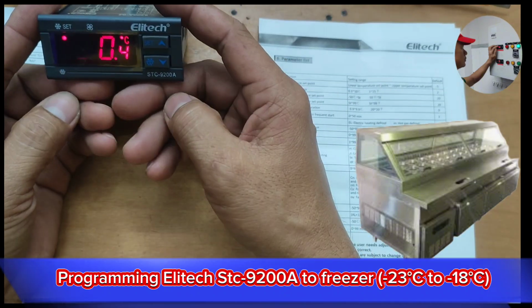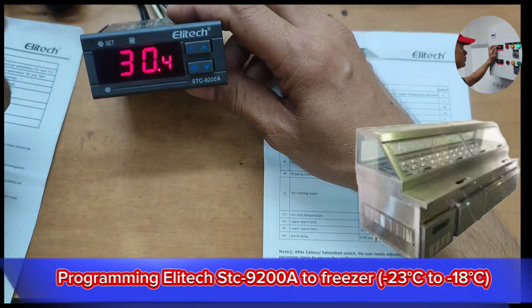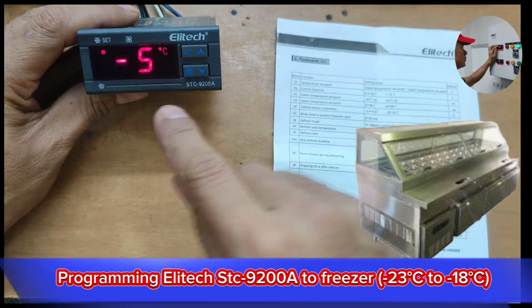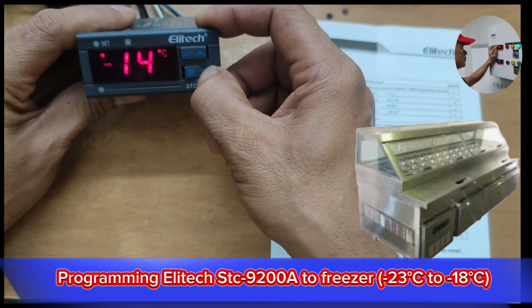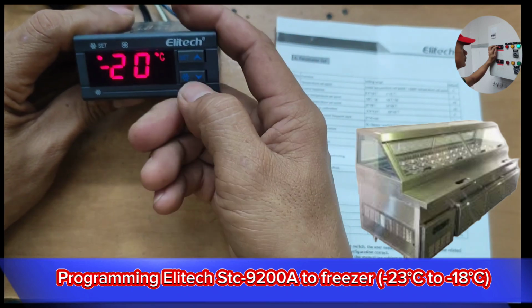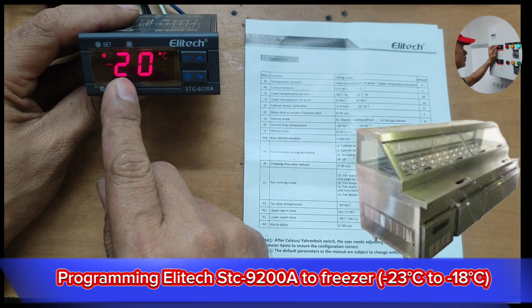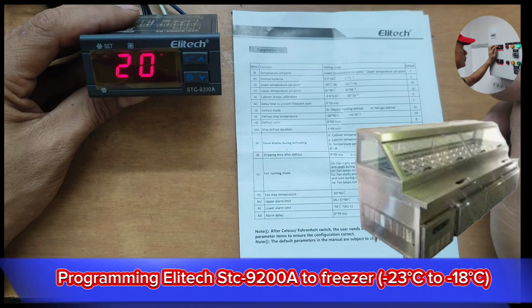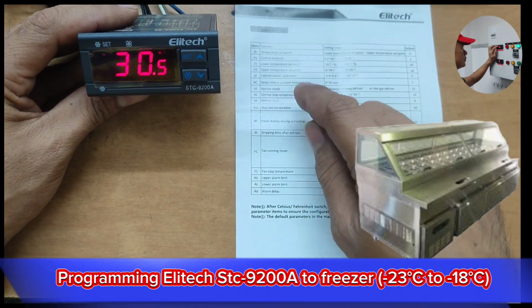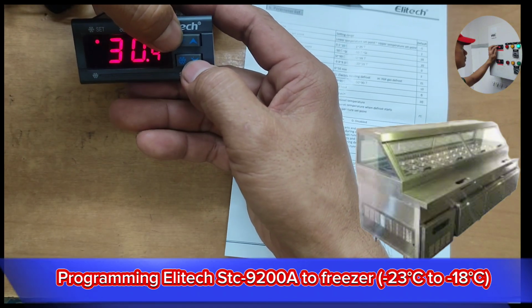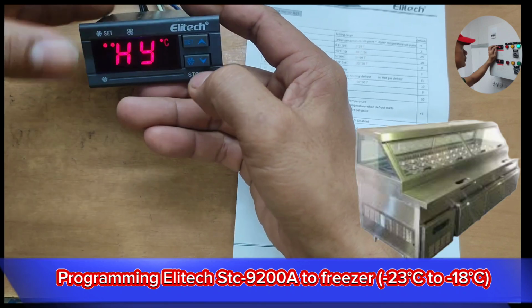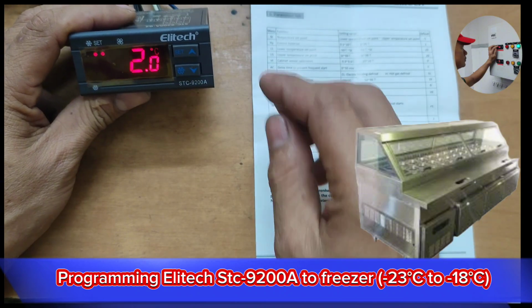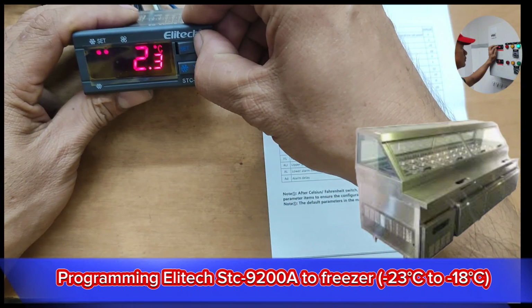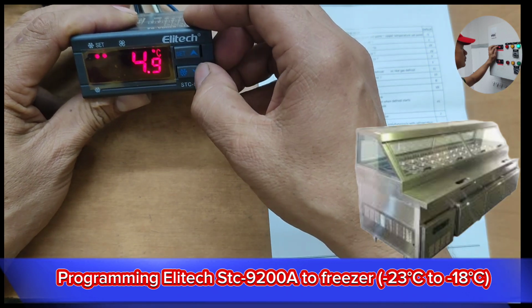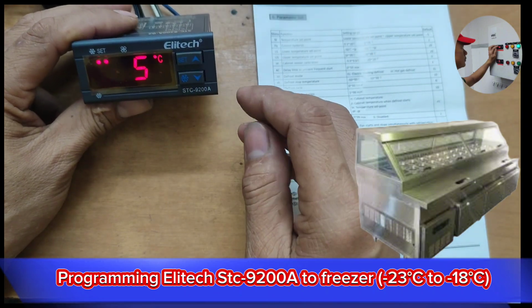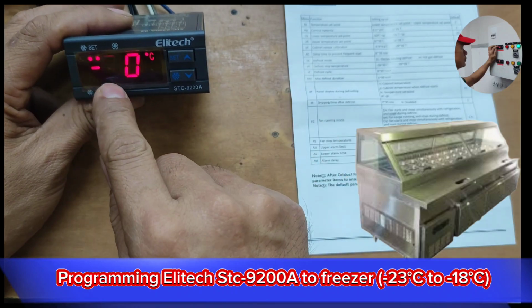First thing to do here is to change the set point, and to do that, just simply press the set button here, and let's change negative 5 to negative 25. Okay, I cannot change it, I can't go beyond, so I'm stuck at negative 20. To enter the parameters, press this button here and the add-on button together, long press, and when HY appears, we can change the HY, and I'm going to program that to 5 degrees Celsius, then reset. And my LS is reset. See, that's why I cannot change.